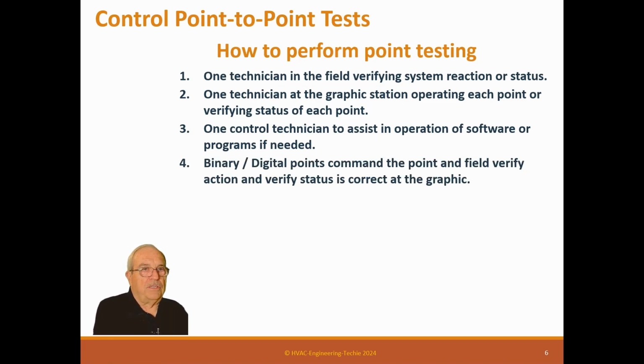Binary digital point: command the point, field verify the action, and verify the status is correct. Like, the guy in the field says, okay, go ahead and start the unit. The guy starts it on the computer and it starts up. Okay, right unit started up. I've done it many times where I start the unit and nothing happens. I say, well, nothing happened. Well, the unit over there started up, so we know that this unit is not that unit, so they've got the units crossed up, and we'll sort that out.